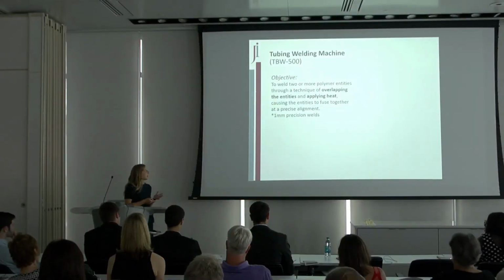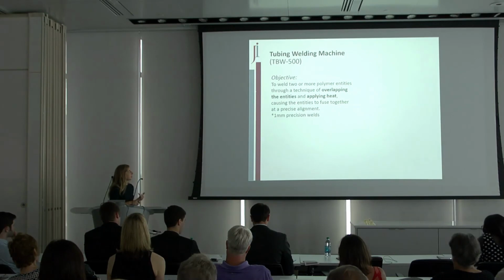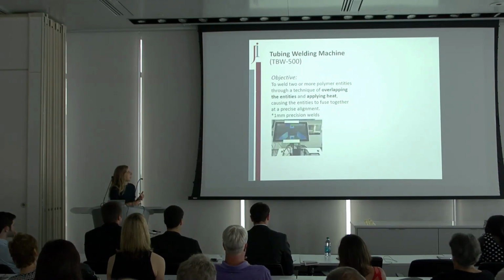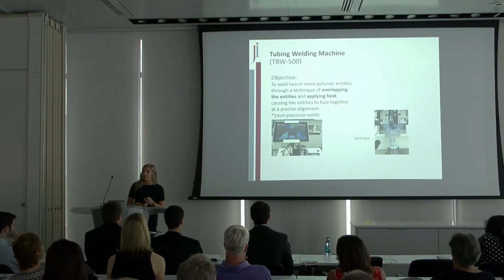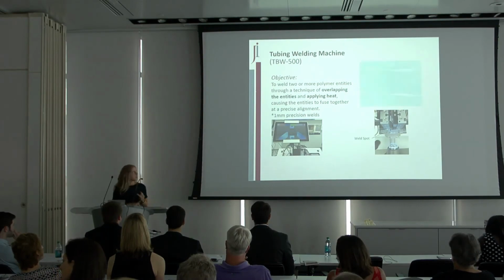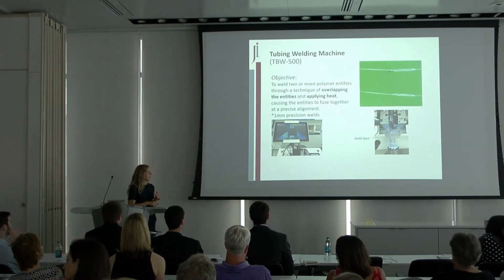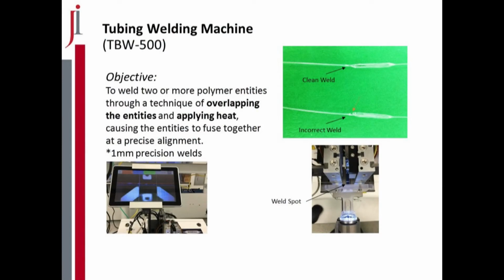And then lastly, looking at our tubing welding machine, this is one of the most versatile machines in that there are 20 steps and 7 of those steps are welding steps. This machine performs 5 of those steps, so it's very, very versatile. As you can see here, this weld spot is a good visual from our camera, as right here, this little light is projected onto a monitor for the user to see.